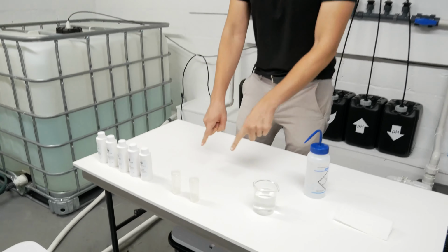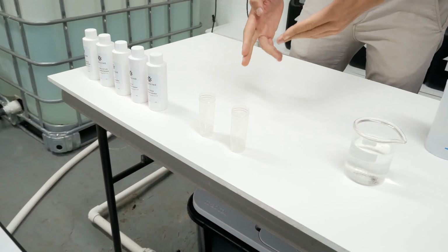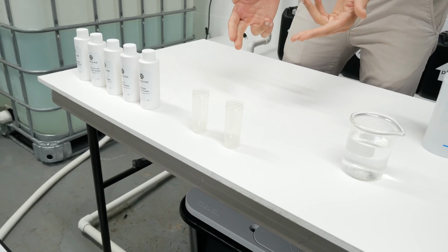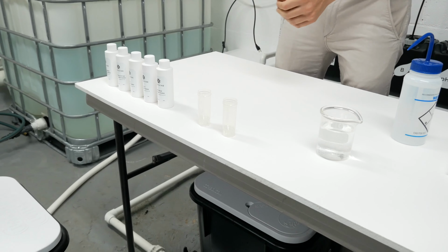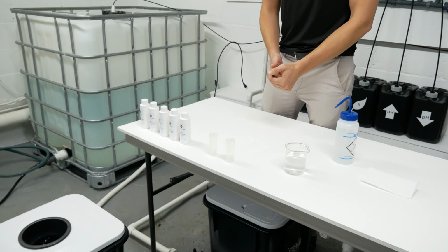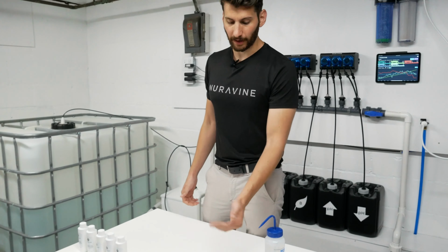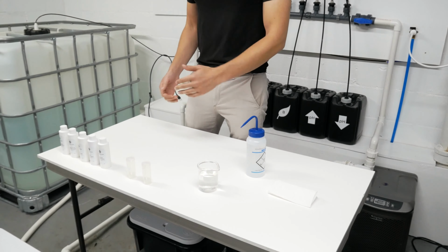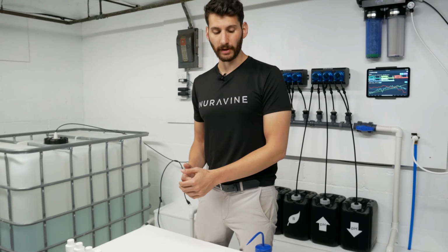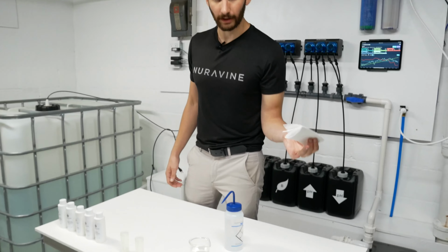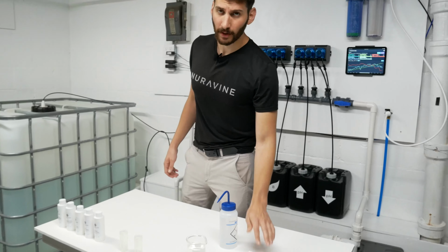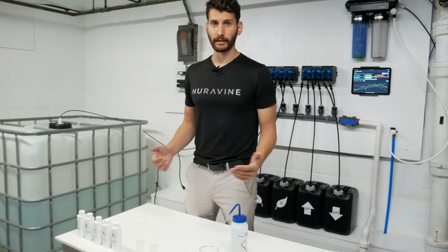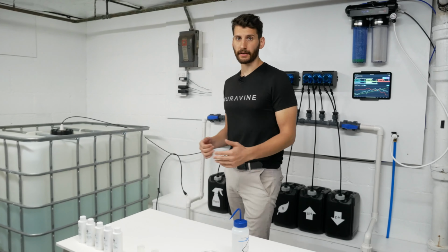Over here we've got 2 different bottles. These are what we're going to put the calibration solution in, and that way we can calibrate our probes without using too much of the solution. We've got a little bit of water right over here so we can rinse out our probes between each individual calibration. Also, I've got a little cloth right here if I need to dry off the probes and clean them up. So let's get started.